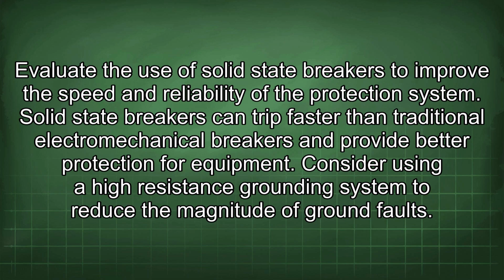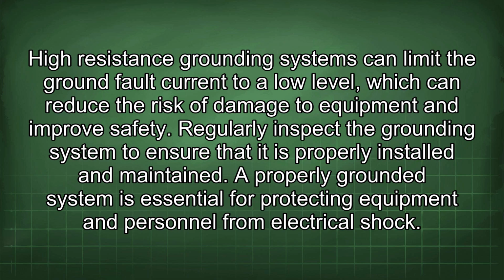Consider using a high-resistance grounding system to reduce the magnitude of ground faults. High-resistance grounding systems can limit the ground fault current to a low level, which can reduce the risk of damage to equipment and improve safety. Regularly inspect the grounding system to ensure that it is properly installed and maintained. A properly grounded system is essential for protecting equipment and personnel from electrical shock.